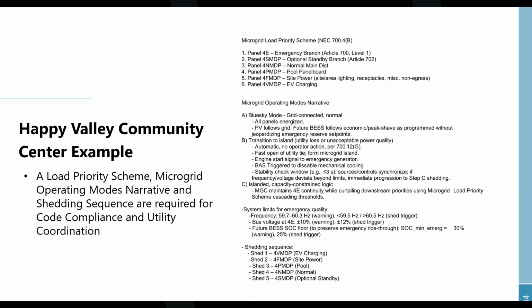This next slide shows what information needs to go along with a single line diagram to describe how the microgrid is going to operate. We need an operating modes narrative that explains what's happening in blue sky mode and grid connected mode, then what happens on loss of utility power or unacceptable power quality from the utility, which usually means you're about to lose it, and how that transitions from blue sky to islanded mode.